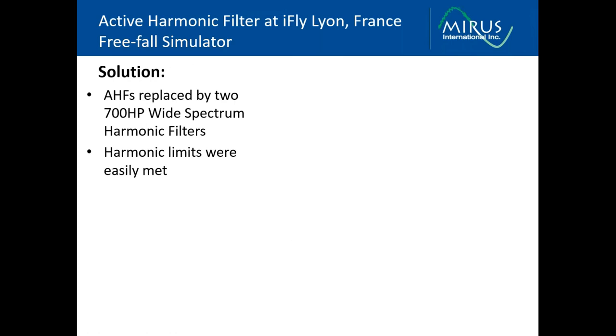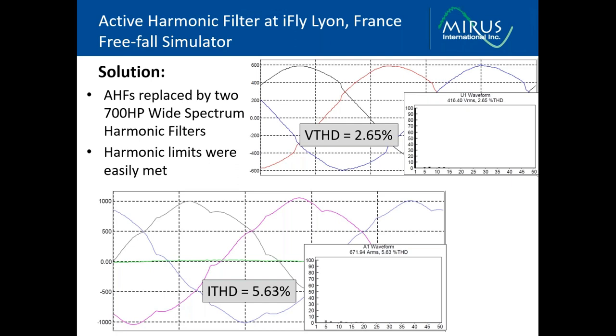So the AHFs were replaced by two 700 horsepower wide spectrum harmonic filters. And with these filters, the harmonic limits were easily met. Here we show that the current distortion was reduced to just over 5%. You can see the current waveform is near linear, and the voltage distortion was reduced to 2.65, well below the requirements by the standards.